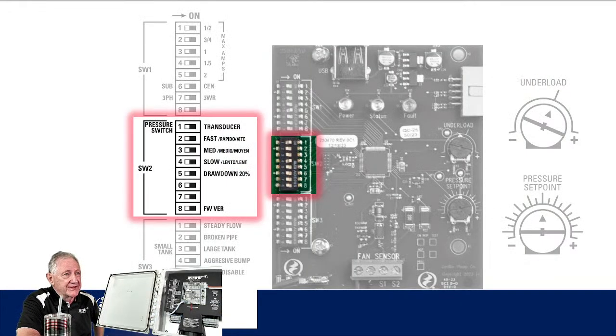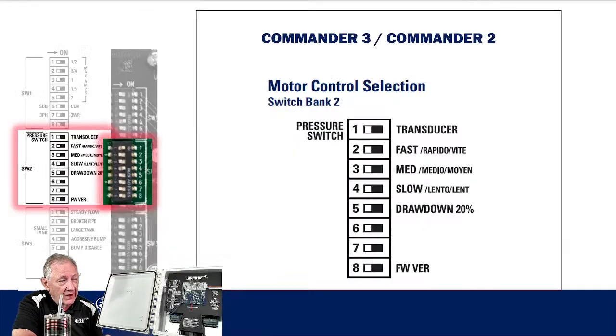If we move down to the second bank, and I mentioned earlier that this second bank has a whole lot to do with what we're going to power that pump motor up with, all right? What are we going to power it up with? Well, obviously we have a choice. If you look up there at that second bank, the very first position, you can either operate a pressure switch or you can operate a pressure transducer, all right? So that's what that first position in that second bank is going to tell us. I'm going to move ahead one slide.